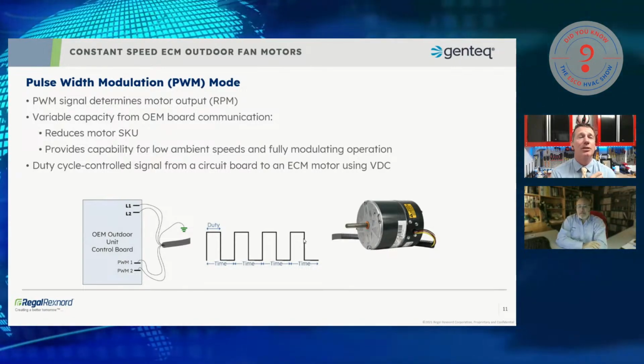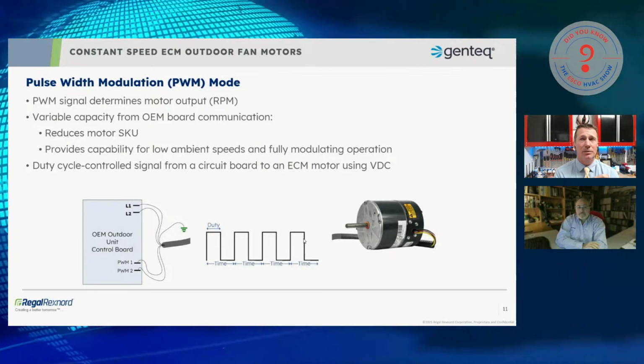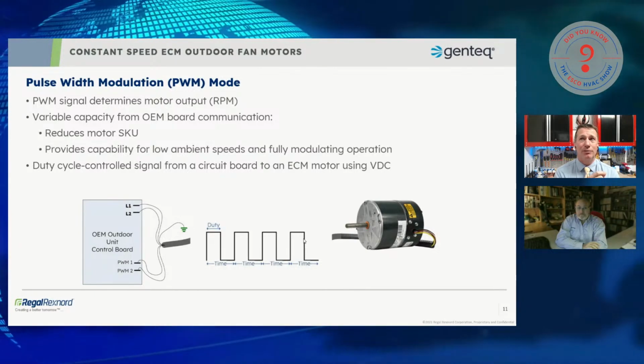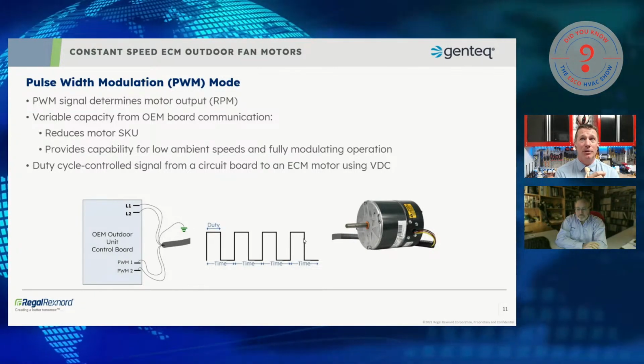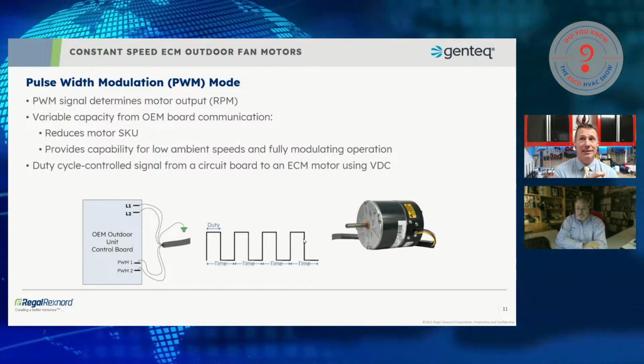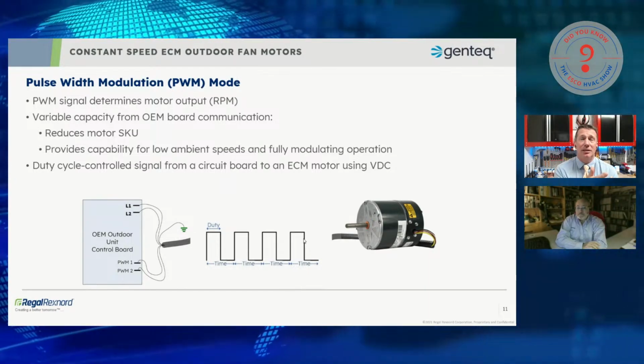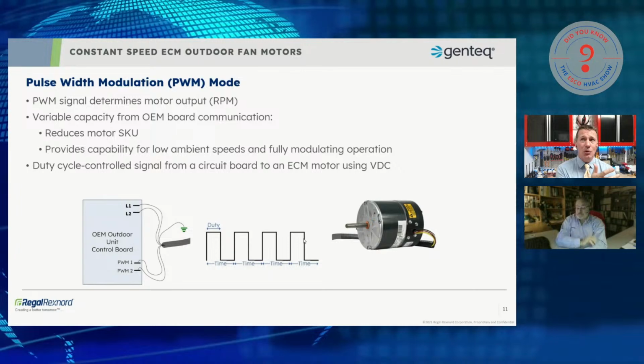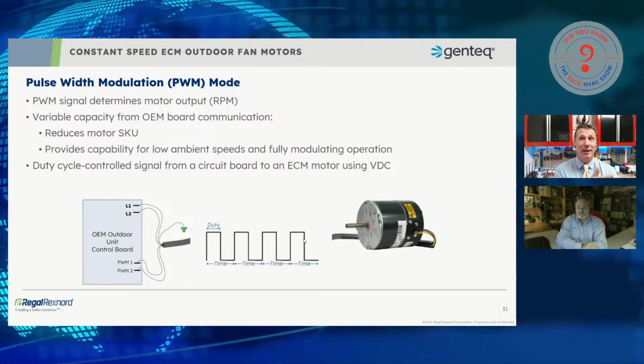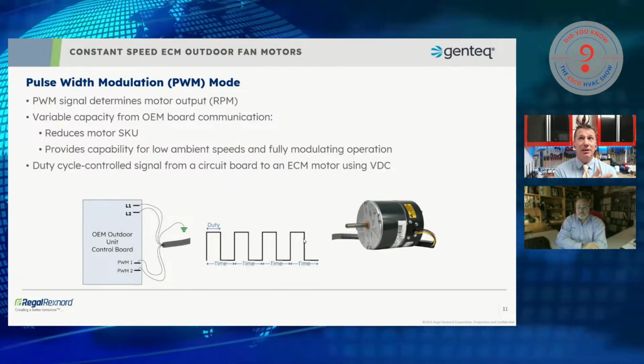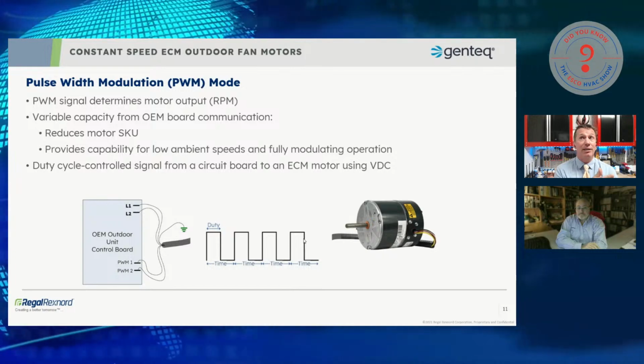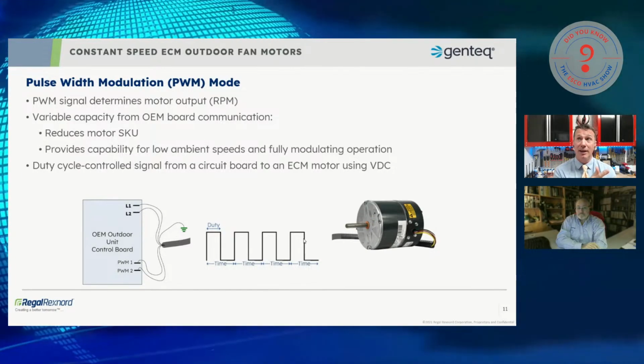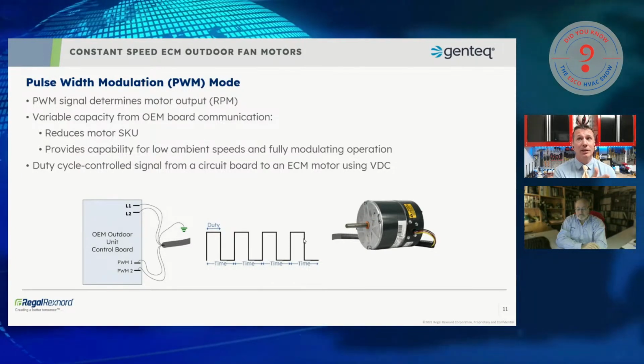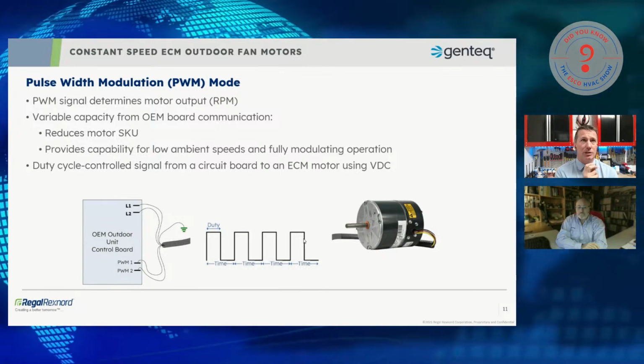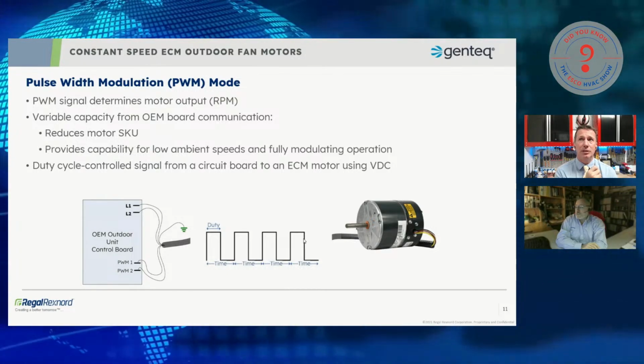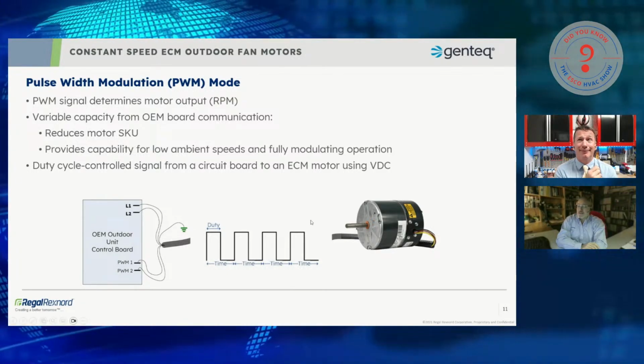So it always comes back to understanding what's in the installation manual, knowing whether we have a 24 volt AC or whether we have a pulse width modulated signal that we would read with DC. And then it's just checking to see that we have high voltage and low voltage again. That's the beauty of understanding ECMs. If I don't have high voltage and I don't have low voltage, I'm not going to work. If I have high voltage and no low voltage, I'm not going to work. If I have low voltage and no high voltage, I'm not going to work. And it's understanding what those voltages look like. You just knocked out my next 5 slides, but that's great. That's a great lead-in. Thank you.